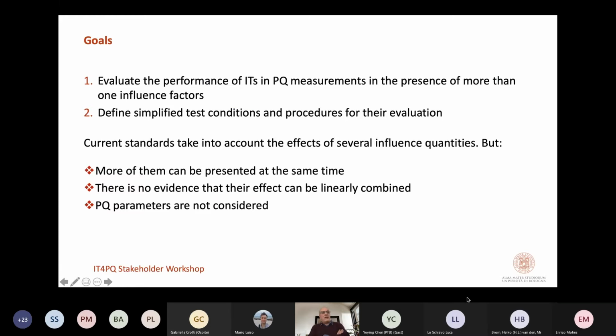Okay, so it is expected that the work package will provide indication on how to evaluate the performance of instrument transformers when measuring power quality parameters, and in particular in the presence of more than one influence factor. And the second, but not less important goal, is to define simplified test conditions and procedures for the evaluation of this performance, given that, of course, we want this project to be of help not only for metrological laboratories or university laboratories, but mainly for industry, that in this connection of course needs simplified but correct procedures to evaluate the performance of the instrument transformers they design and sell.